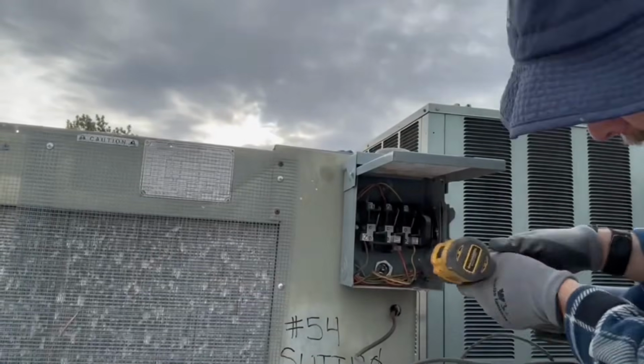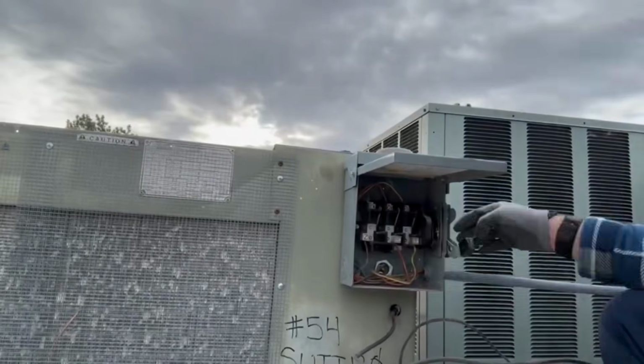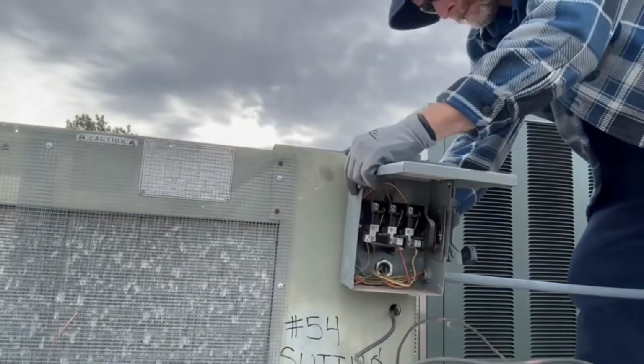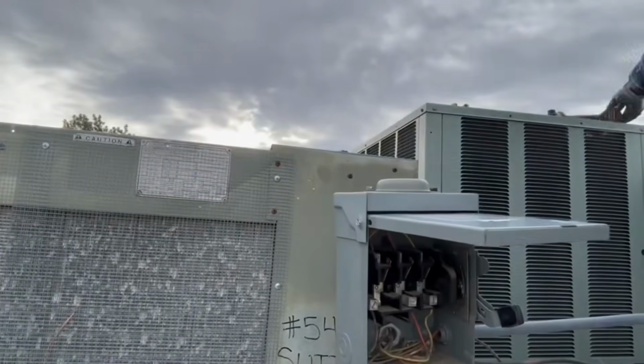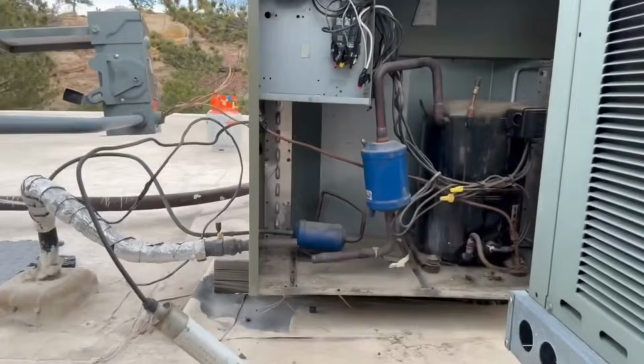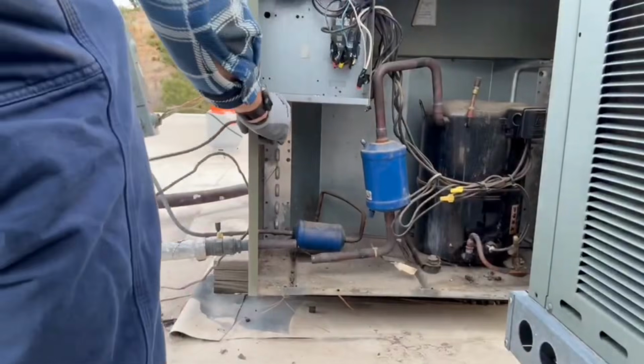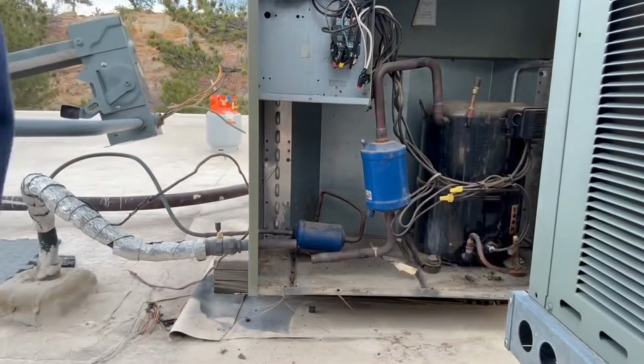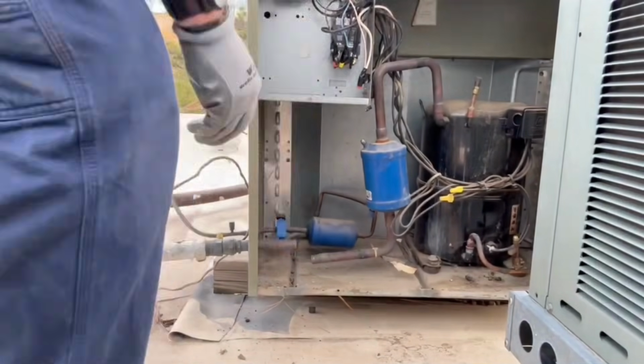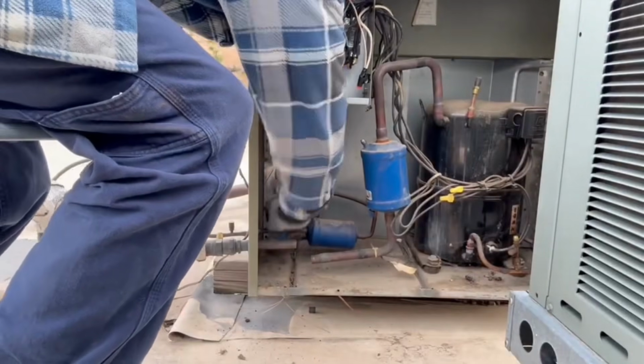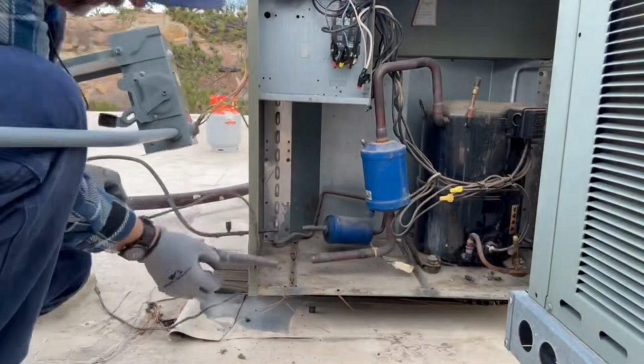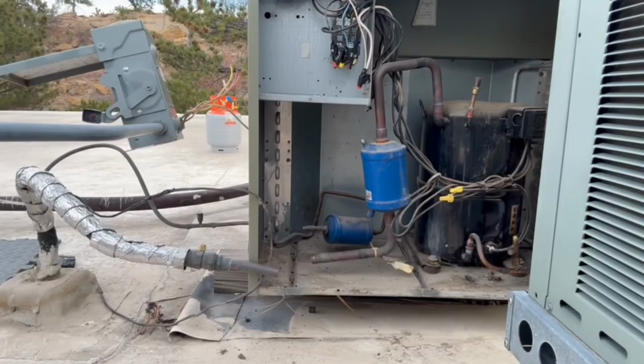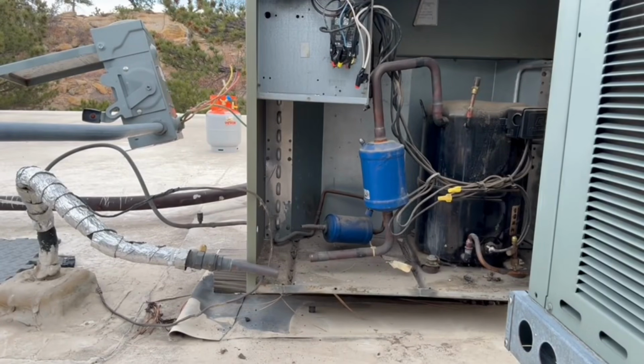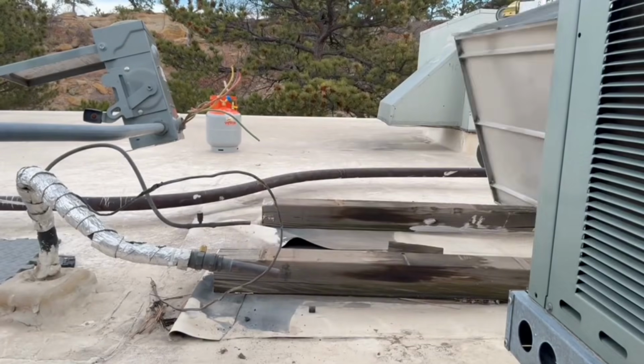Again, I'm just simply going to disconnect the disconnect switch from the side of the old unit, because we're going to reuse it. The power is off. We have it off at the circuit breaker. And I'm simply cutting the copper tube on the suction line and discharge line. I'm going to gently pull those out of the unit. Now everything's disconnected. Got to pull the unit out of the way and get it ready for the crane.